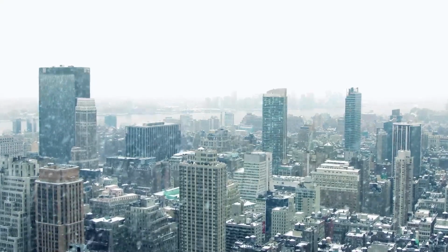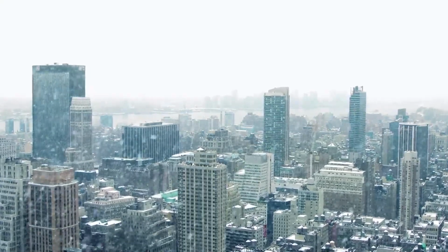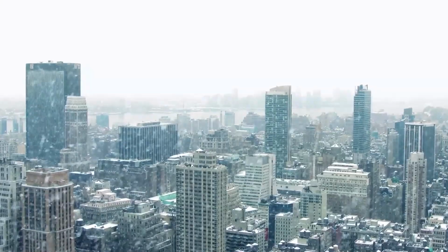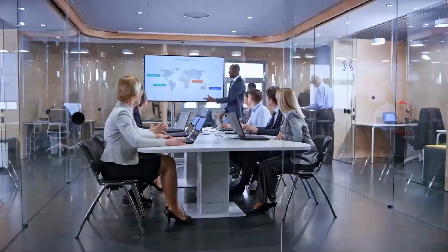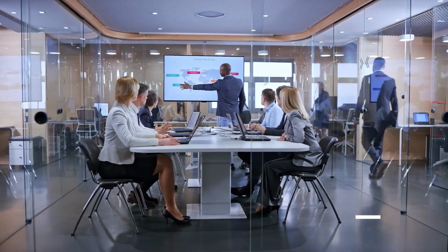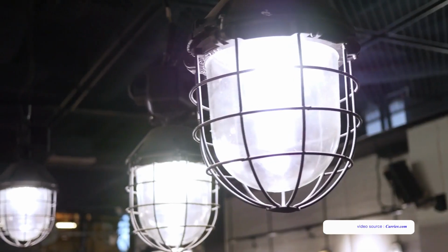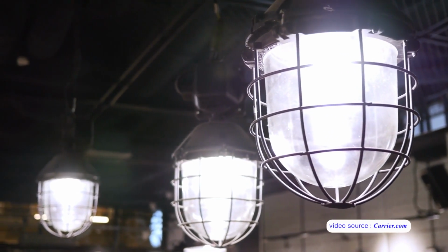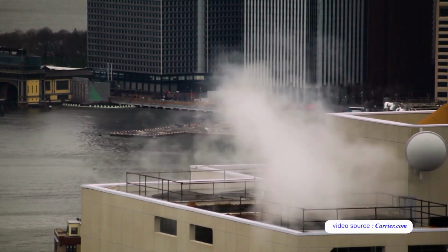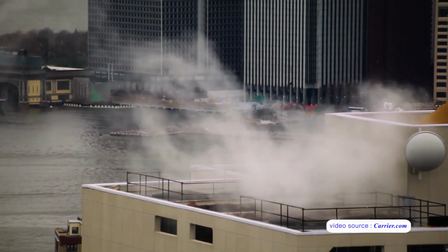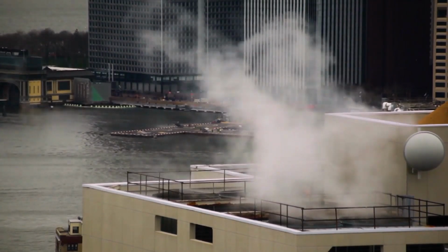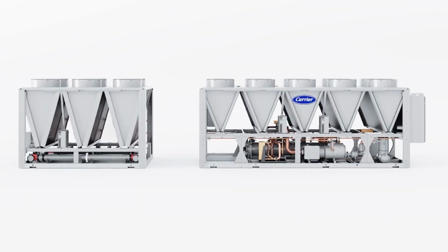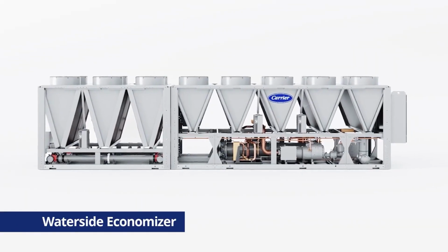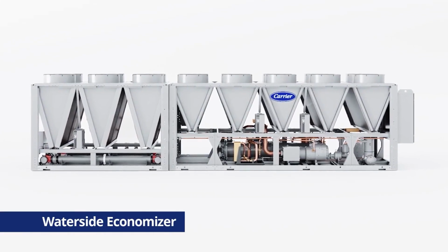While it may not seem obvious, in many HVAC applications, there's a need to provide cooling even in colder months. This is typically due to the internal loads driven by people, computers, machinery, and lighting. Running a chiller year-round is one way to meet that need, but doing so can be costly and inefficient. Another solution is to operate a water-side economizer, sometimes known as a free cooling system.